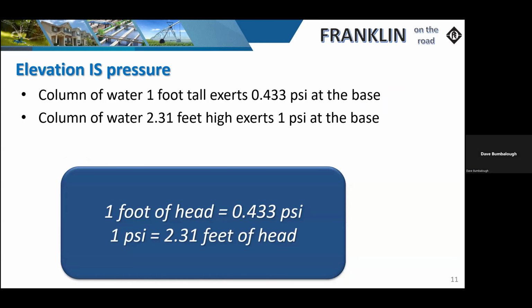The two calculations that you will need to memorize or write down and use. One of them I use most often. I hardly ever use the top one, which is the equivalent to 1 foot of water column. So it takes into consideration just what that 1 foot is going to exert in pounds per square inch at its base. And in this particular exercise, 1 foot of water column will basically equal 0.433 psi at its base. So it doesn't matter if you're looking at an ocean or a swimming pool or a glass of water. At its base, it is what we're actually measuring, and it's pounds per square inch, psi.